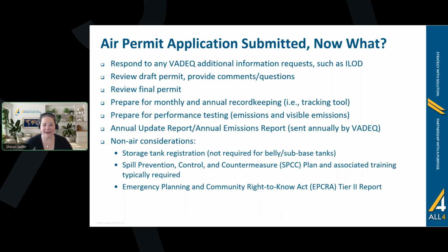And then not just air, right? You have a whole lot of storage tanks that usually come with diesel generators. Just a note, in Virginia currently belly tanks or sub-base tanks aren't actually required to be registered under the oil program, but they certainly need an SPCC plan. That 1320 gallons of above ground storage goes pretty quickly with a portion of one belly tank for a big generator. So you're usually going to need an SPCC plan, but you don't normally need a state registration of any kind, and usually storage tanks are exempt from air permitting.